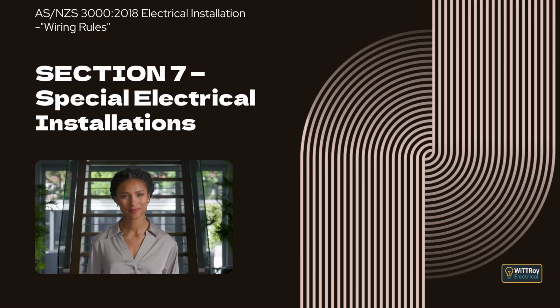Clause 7.2.2.3.1 Continued occupation. This clause explains that where an alternative supply is provided to allow people to remain safely in a building, it must be capable of supplying both safety services and the electrical equipment needed for continued occupation during a loss of normal supply. Clause 7.2.2.3.2 Fire Management System. This clause explains that when a fire management system is used to control safety services, it must be connected to the alternative supply. The alternative supply must have enough capacity to operate all the required safety services in fire mode, including allowances for starting motors or staged operation of equipment.